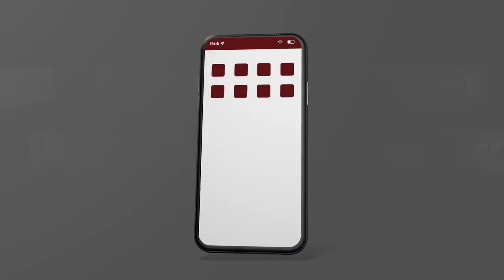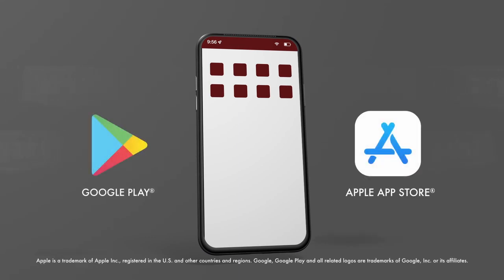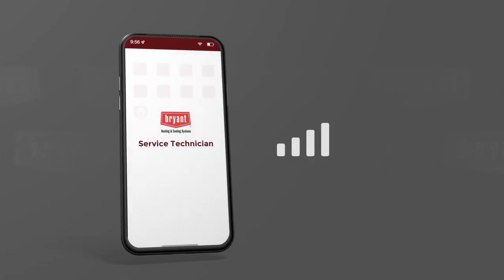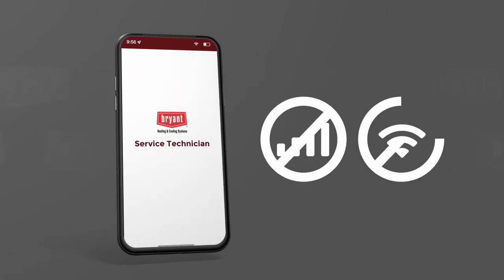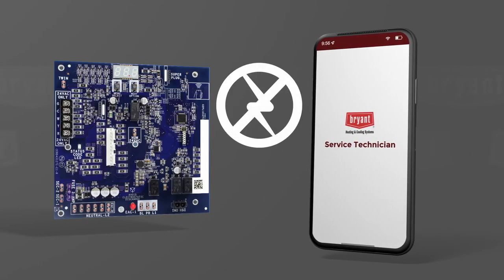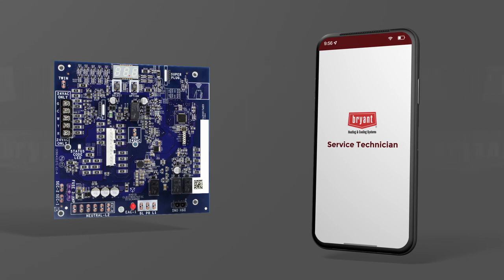To explore this new technology, download our free tech app from the Google Play or Apple App Stores. Once the app is downloaded, you don't need cell service or Wi-Fi to utilize NFC. Specifically, the functions for installer setup and accessing diagnostic information don't require a signal. The control board does not need power — in fact, the power must be off when utilizing NFC communication. Your mobile device activates the NFC antenna on the control board when in very close proximity.